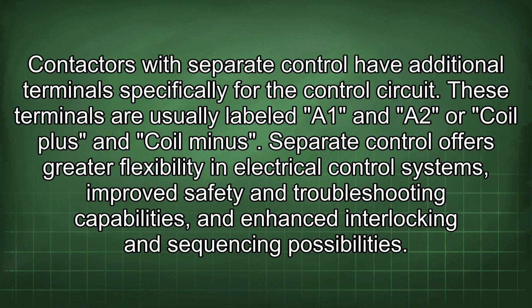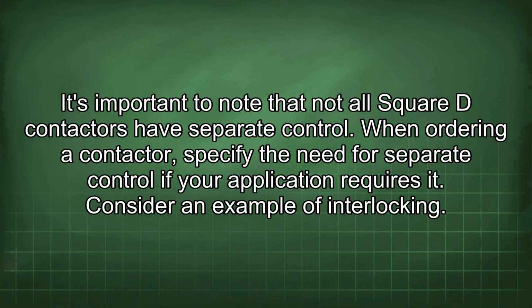Contactors with separate control have additional terminals specifically for the control circuit. These terminals are usually labeled A1 and A2, or coil plus and coil minus. Separate control offers greater flexibility in electrical control systems, improved safety and troubleshooting capabilities, and enhanced interlocking and sequencing possibilities. It's important to note that not all Square D contactors have separate control. When ordering a contactor, specify the need for separate control if your application requires it.